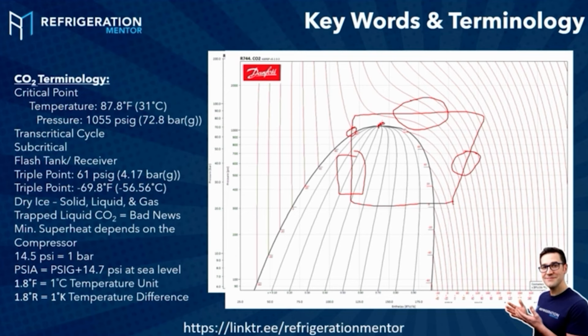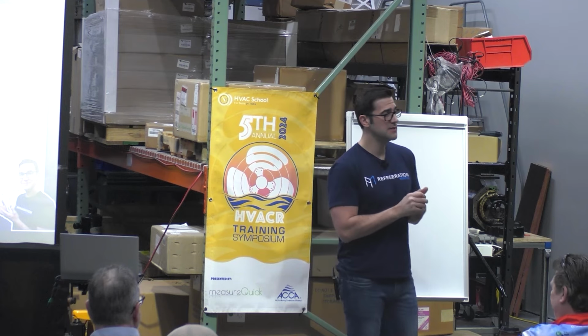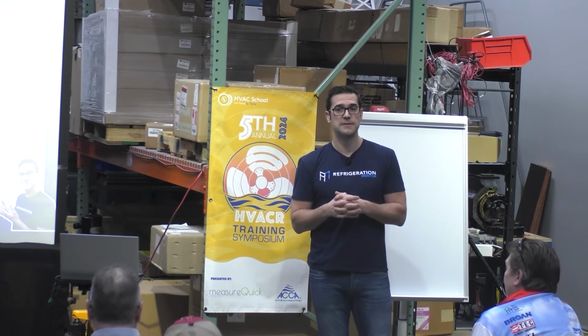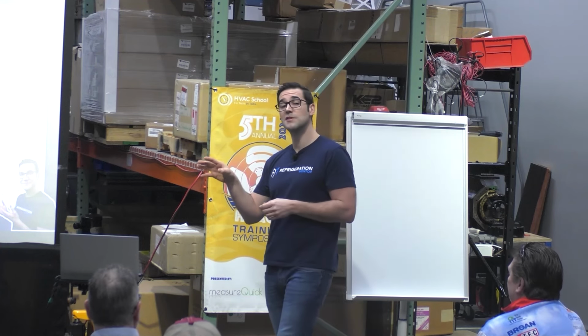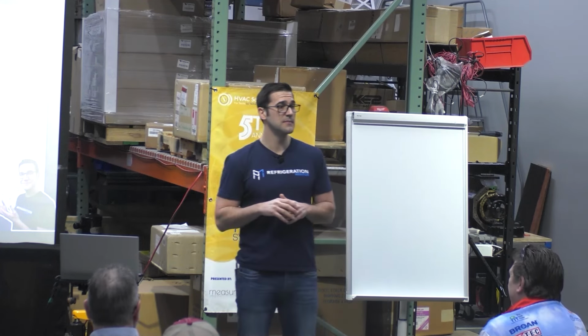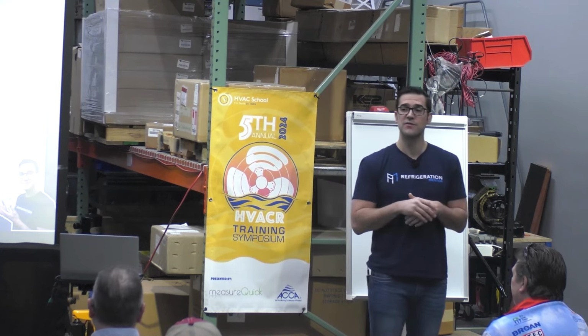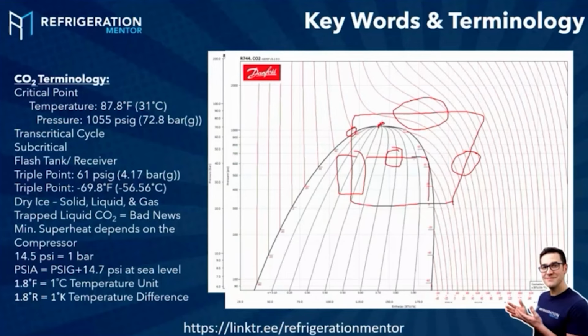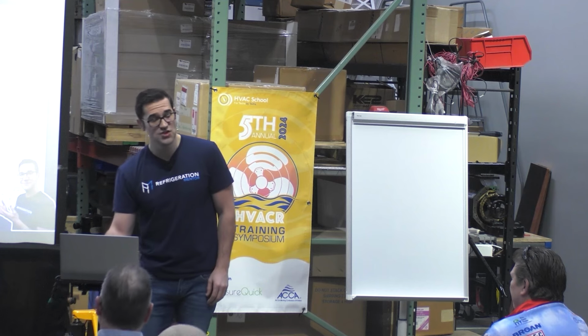This liquid now gets to feed, and what's cool about CO2, it gets to feed both your medium temp systems as well as your low temp systems. An even cooler part about CO2 is you can do air conditioning and heating all in one system because there's a really high heat index for CO2. So the way this works is that now I have my liquid line, my liquid here coming from here. On the top, there's gas. This is called flash gas. So we have some gas. The vapor comes off the top to a valve right here, which is called a flash gas bypass valve. Once again, it's just a valve.